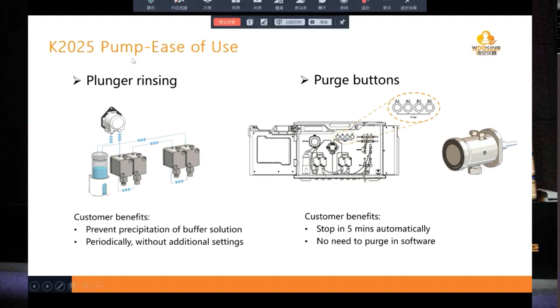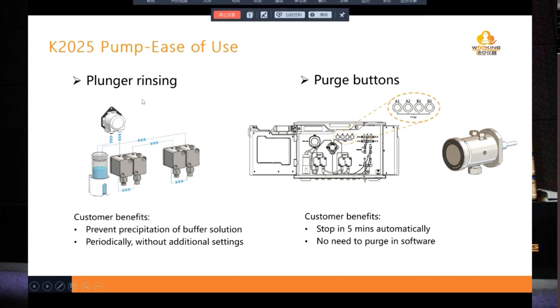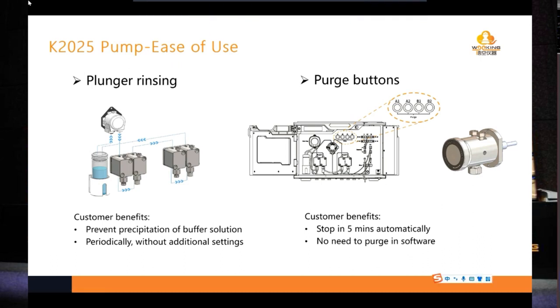There is a plunger rinsing mechanism built in the pump. It is designed for the flushing of the plunger and the plunger seal. The rinsing solvent is prepared by the users, not by others. We recommend using 10% isopropanol.